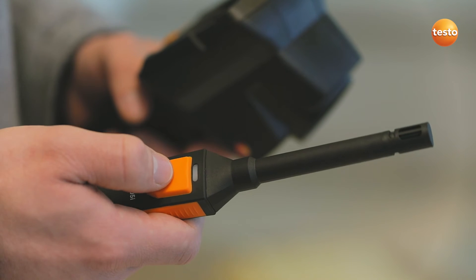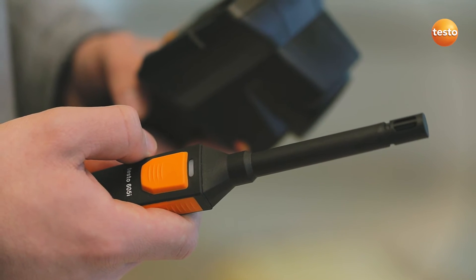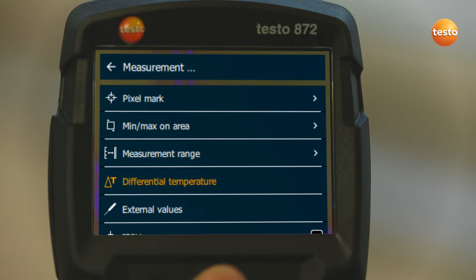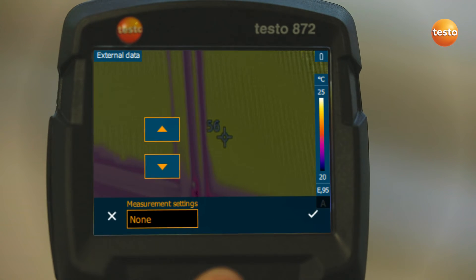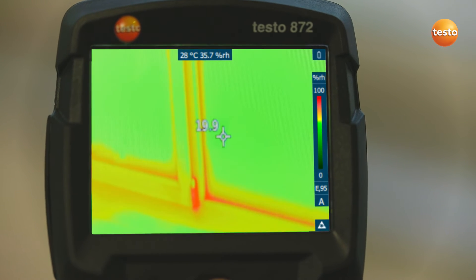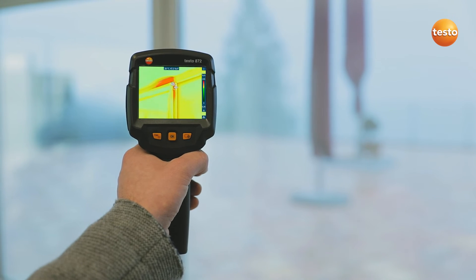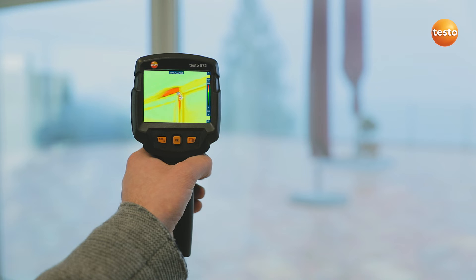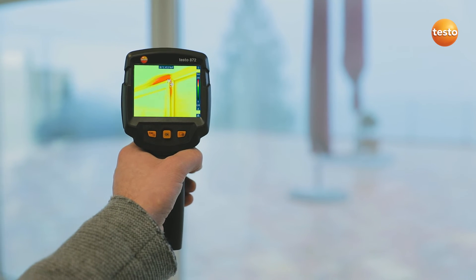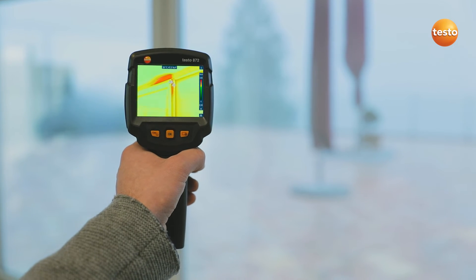In order to detect mold better, the imager integrates the air humidity and temperature values measured with the thermal hygrometer Testo 605i into the image. In combination with the thermal imager's special humidity palette, this enables you to identify mold risk really easily, based on the traffic light principle. Here, the traffic light is red — that means acute mold risk for this measurement object.